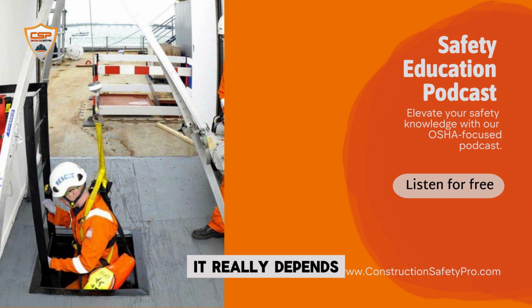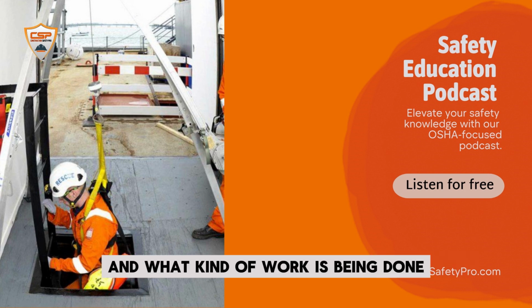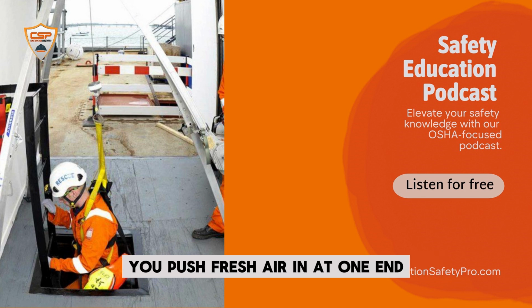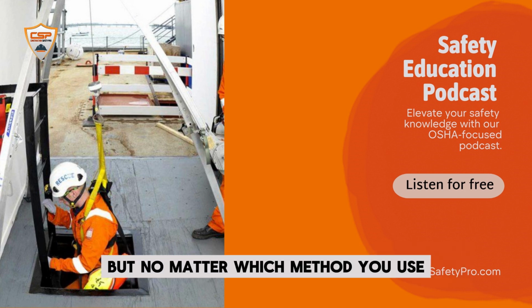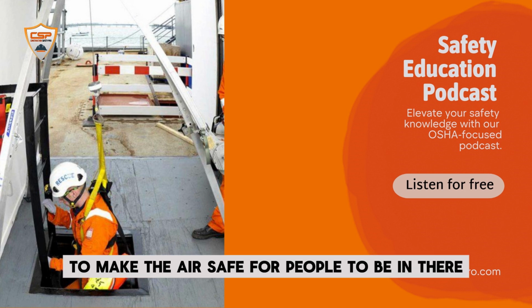It really depends. The best way to go depends on the space itself, the kind of hazards you've got, and what kind of work is being done. Sometimes the best solution is to use a combination of both. That's what we call a push-pull system. You push fresh air in at one end and pull the dirty air out at the other, creating a constant flow of air through the space. But no matter which method you use, the goal is always the same: to make the air safe for people to be in there. Right.